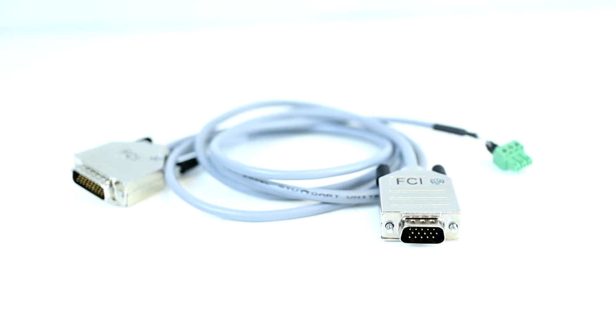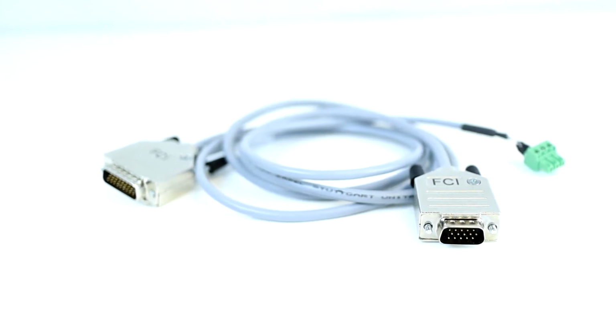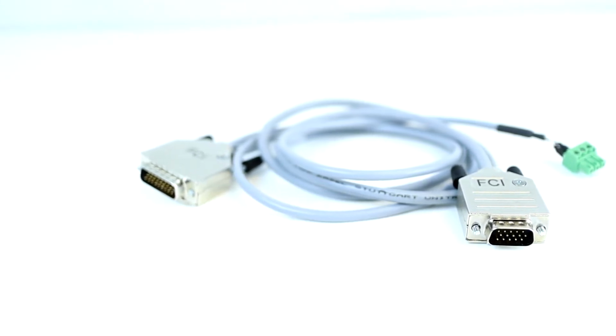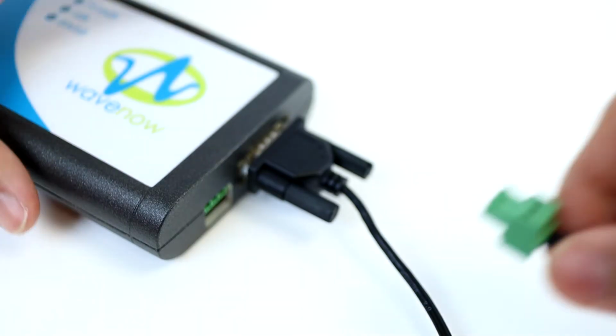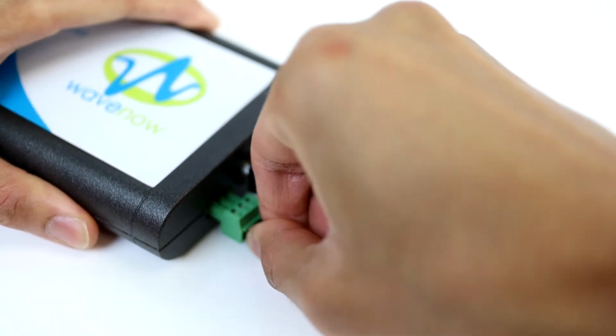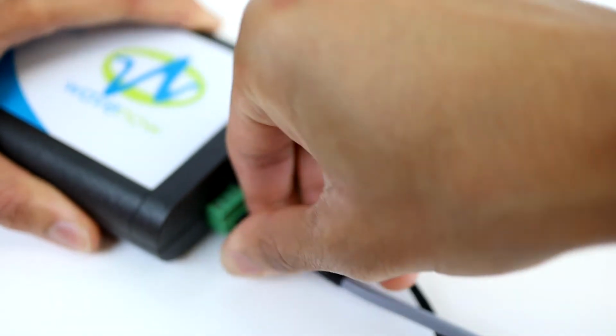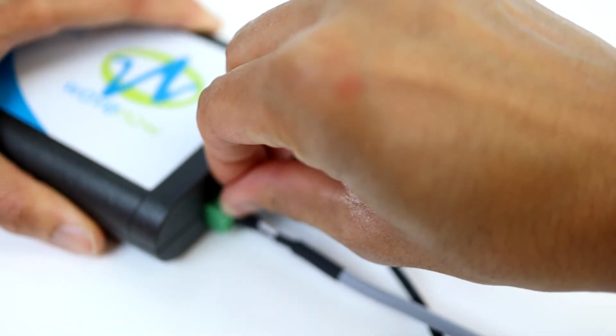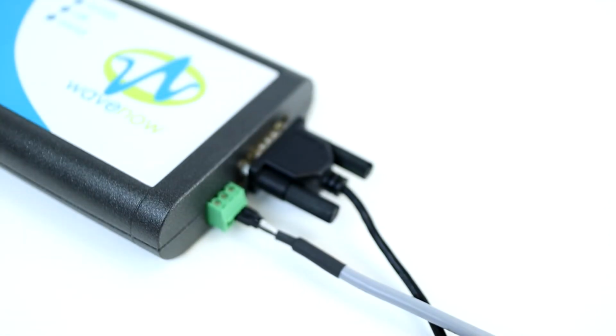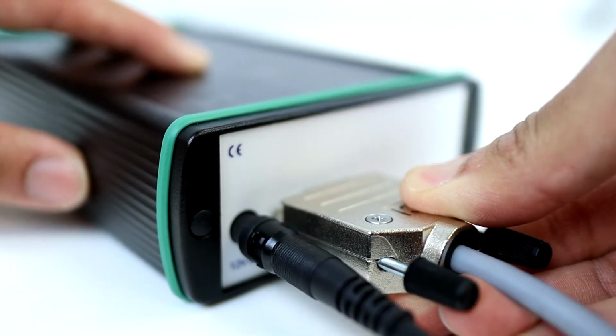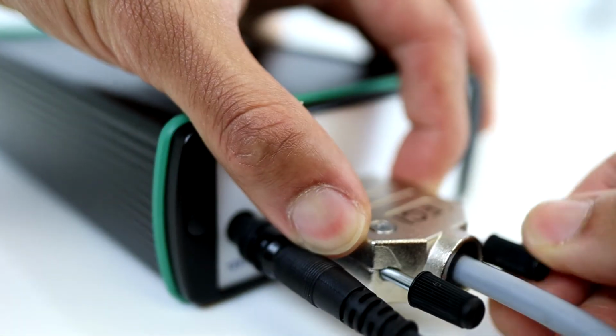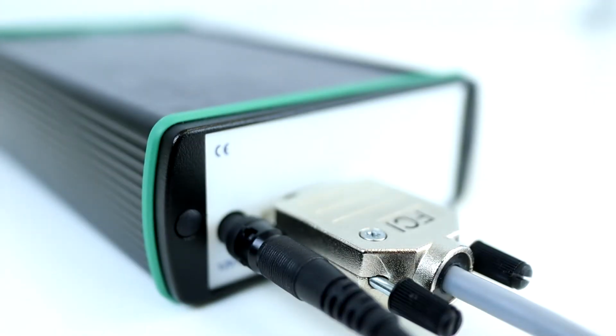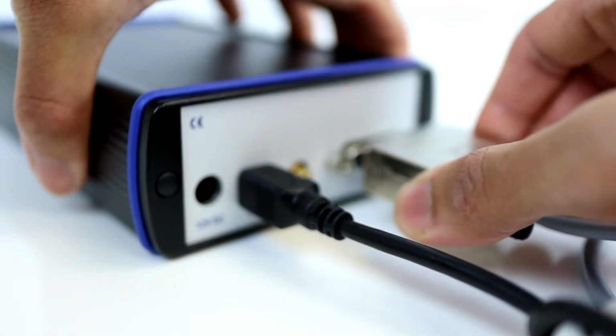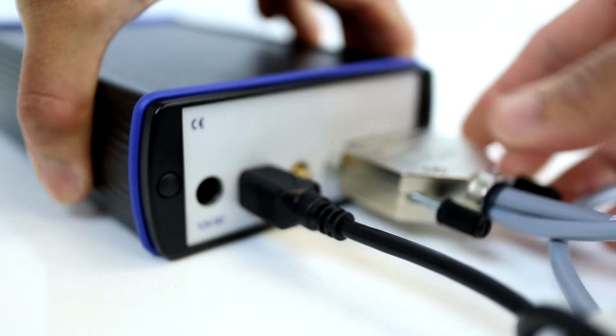Next, we will use the integration cable to connect the potentiostat, spectrometer, and light source together. Connect the green block connector to the potentiostat. The 15-pin D connector to the light source. And the 26-pin D connector to the spectrometer.